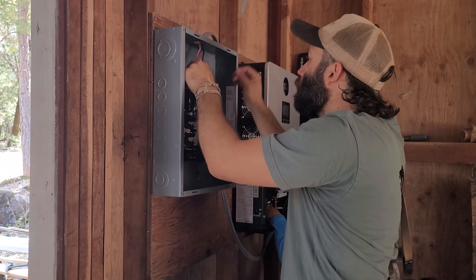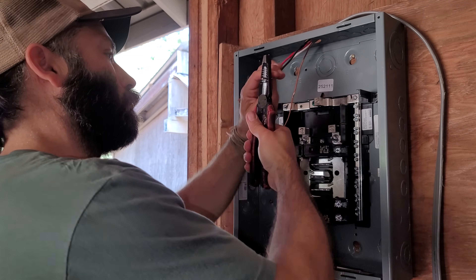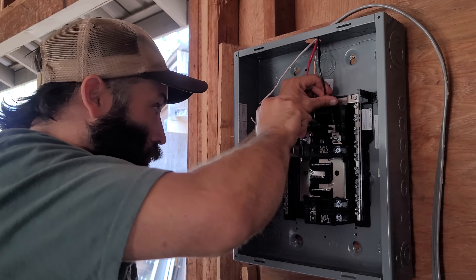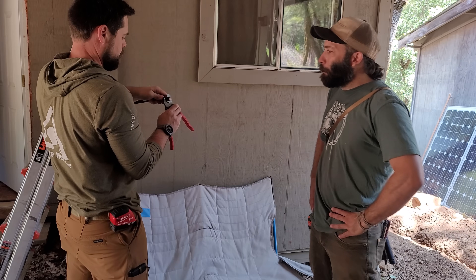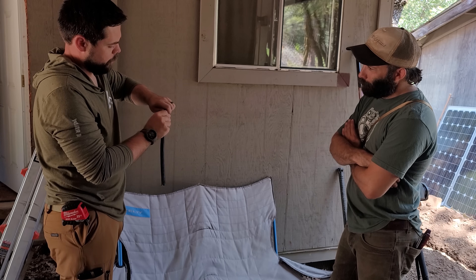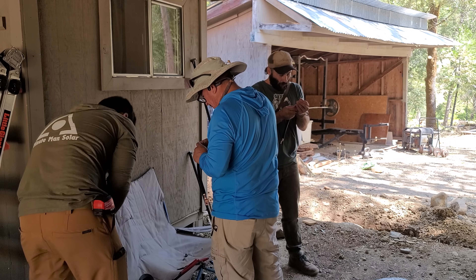This is a 6000-watt inverter, and this is an off-grid project with no permits or paperwork being done. We wired the main electrical panel using four wires: a red, black, white, and ground. I let Clutch do a lot of the work — I wanted to make sure that he felt comfortable knowing how their system worked, and he was very interested in being a part of the installation. We decided to make the red wire leg one or phase one, and the black wire leg two or phase two. I recommend buying your battery cables pre-terminated with battery lugs already on them, but we chose the harder option of making our own cables for this project. I showed Clutch and Alex how to put the cables together. It's important to make sure you don't have any loose wires sticking out from the battery lug so that as much energy as possible moves through the cables properly.